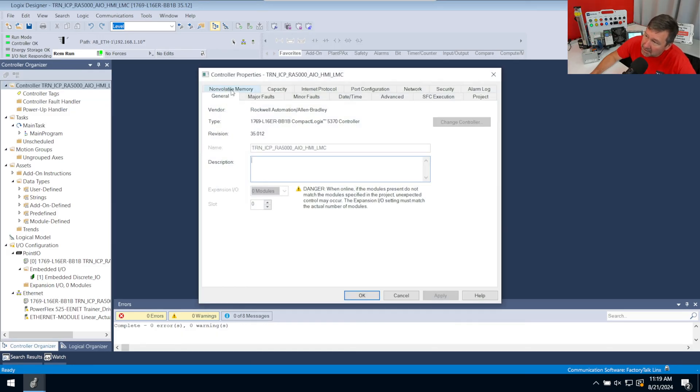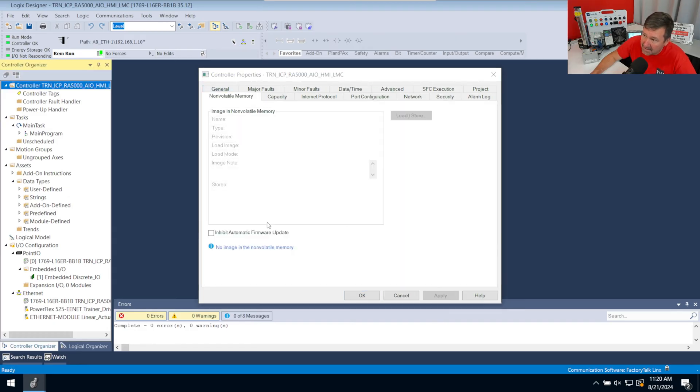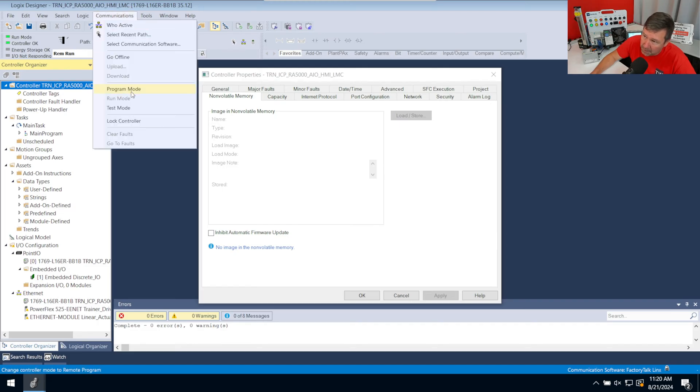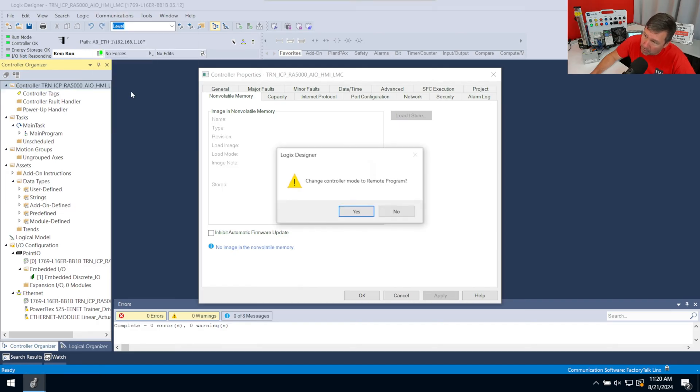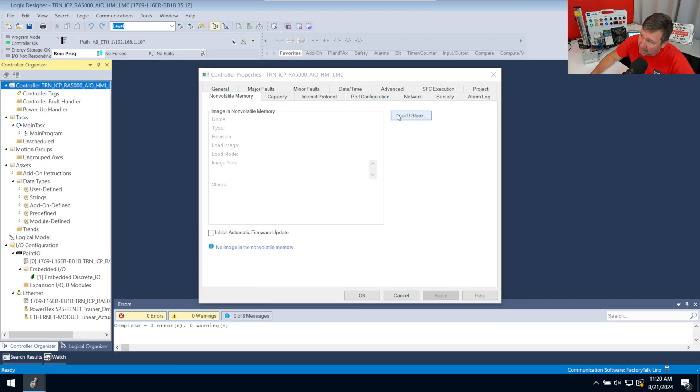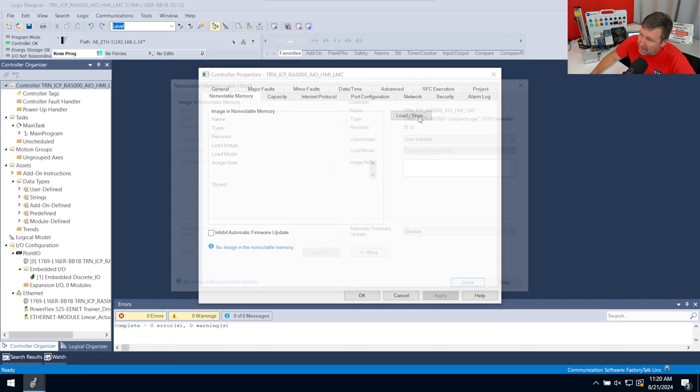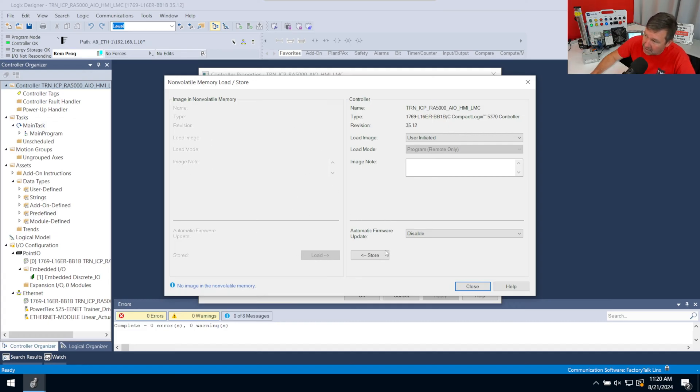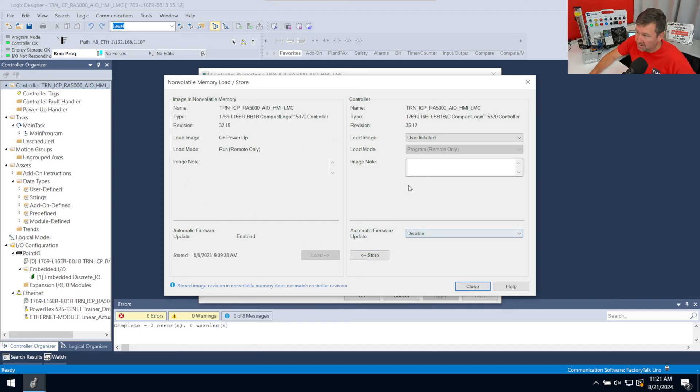And then we want to go to the Non-Volatile Memory. And it says no image in Non-Volatile Memory. But right now, we have a Load Store button here that is grayed out. And it's grayed out because we're in Run Mode. So we're going to go to Communications and we want to put it in Program Mode. And that's going to make the Load Store button available. I'm going to click on it. And so we can load the image if it actually had something stored on the Compact Flash. Or we can store it, which means we can put it onto the Compact Flash. So I do want to store it, but there's a couple of things we need to do.